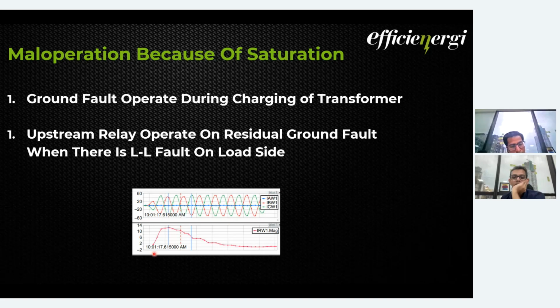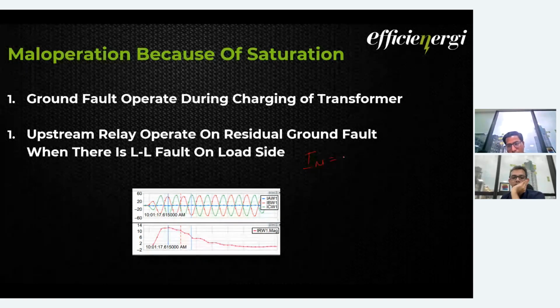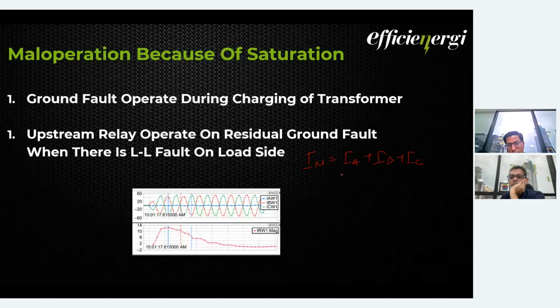The residual basis calculation means IN is IA plus IB plus IC. If everything is perfect, then IN will be 0. But suppose one of the CTs is not showing the exact current, or it gets saturated. Then this will bring in an unbalance, and IN will be greater than 0.